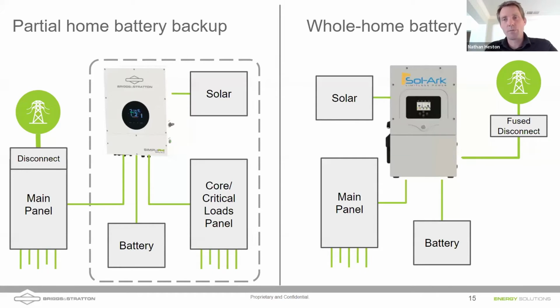Let's contrast that with whole home backup. What do we mean by whole home backup? So the Sol-Ark 15K is shown there on the right side of the screen, and it's connected to the grid as well. What happens in a grid down situation here? Well, first off, notice that there's only one loads panel there. It's just that main panel. The entire main panel is going to be supplied by power that is run through the Sol-Ark 15K inverter. Of course, you have a battery as well to make it an energy storage system.